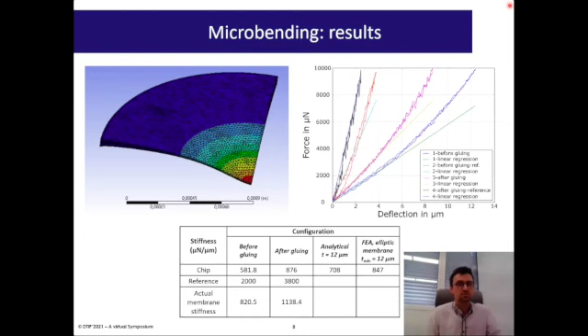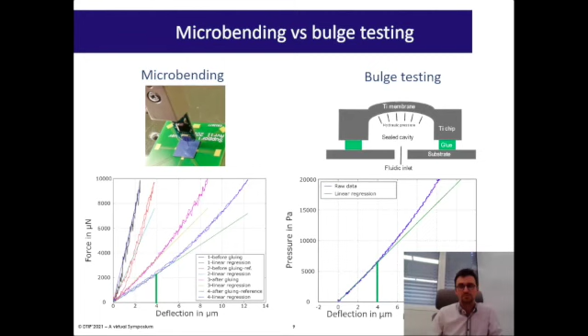The microbending results were also compared qualitatively to previously obtained bulge test results for the same chip. What can be seen is that there is a good agreement between the previous results and the new ones. Indeed, in both cases, a non-linearity becomes significant at around 4 microns of deflection, which shows a good consistency of the experiments.